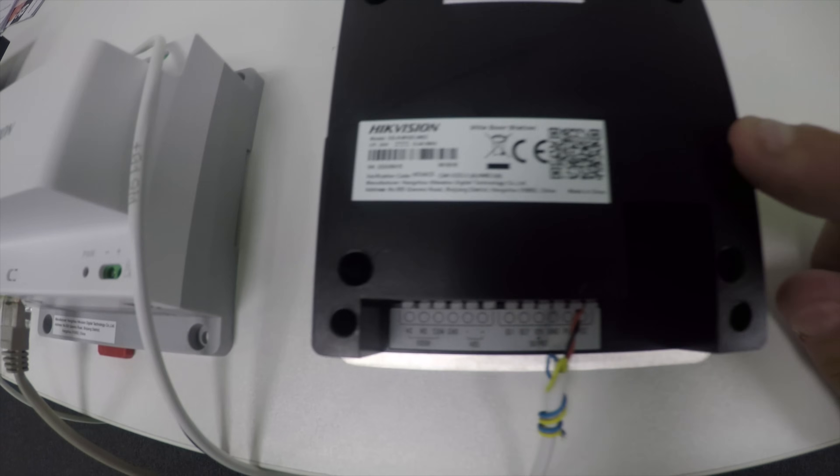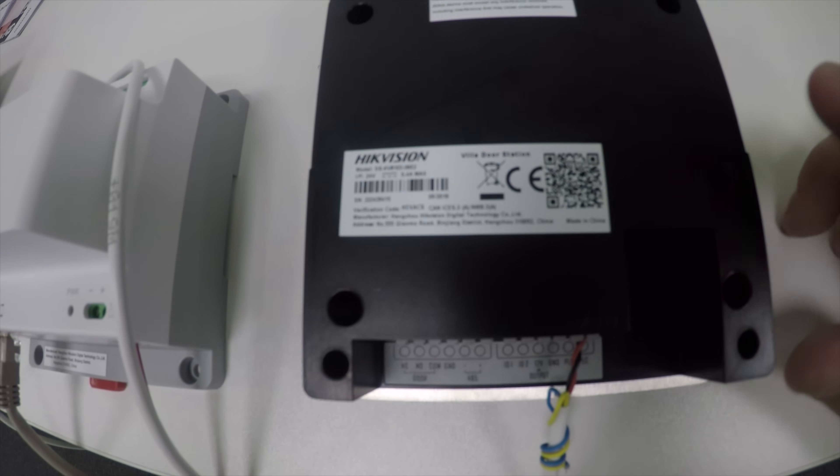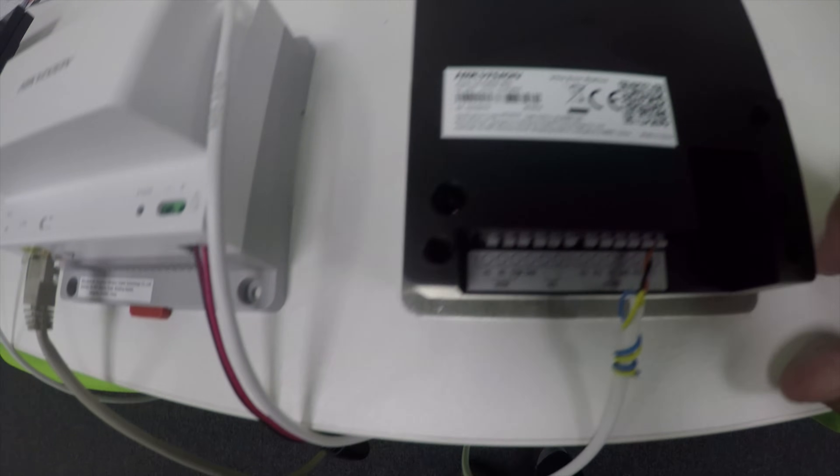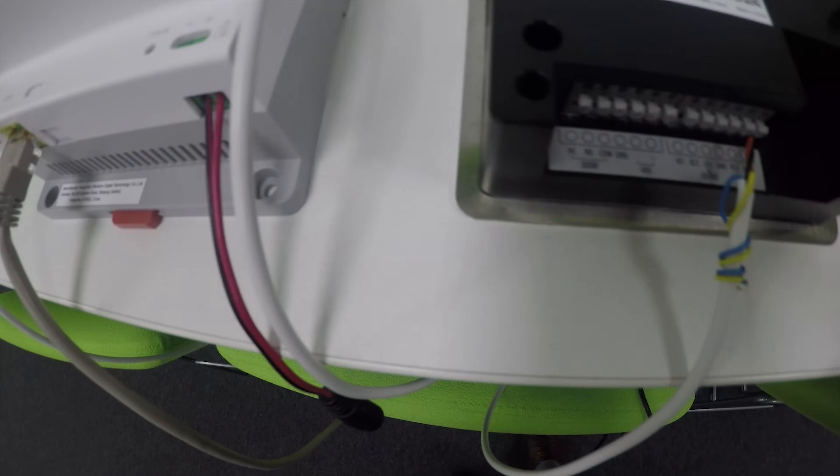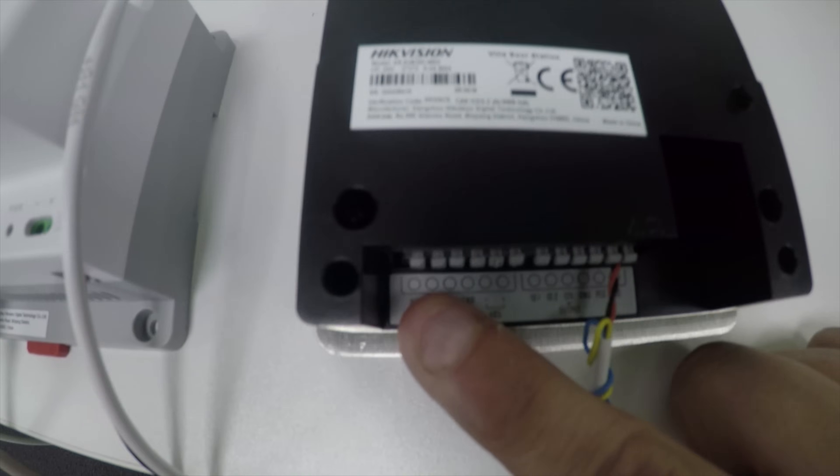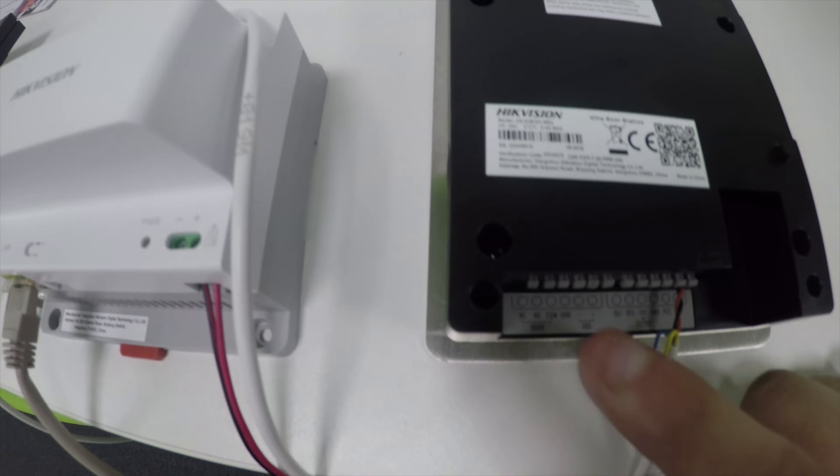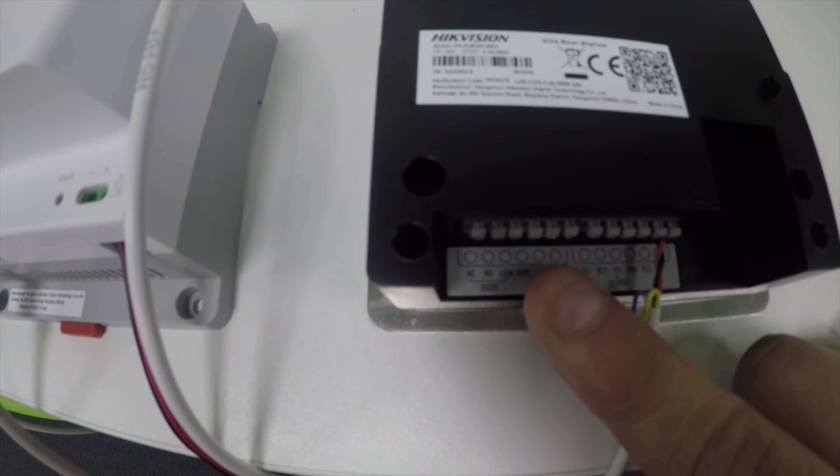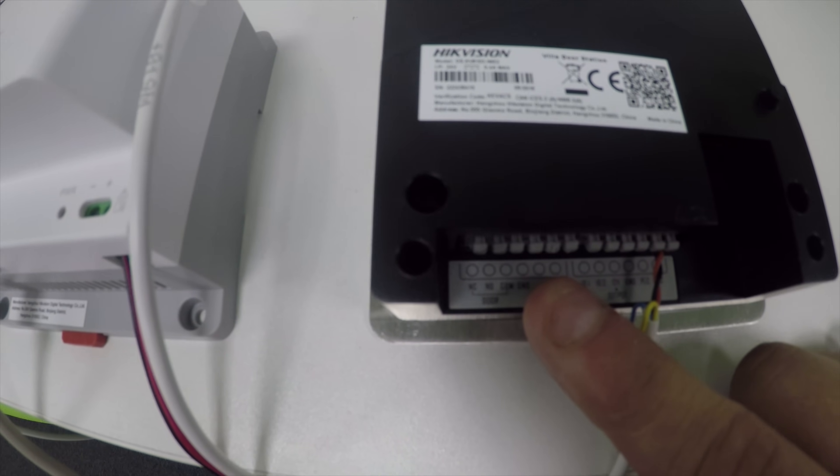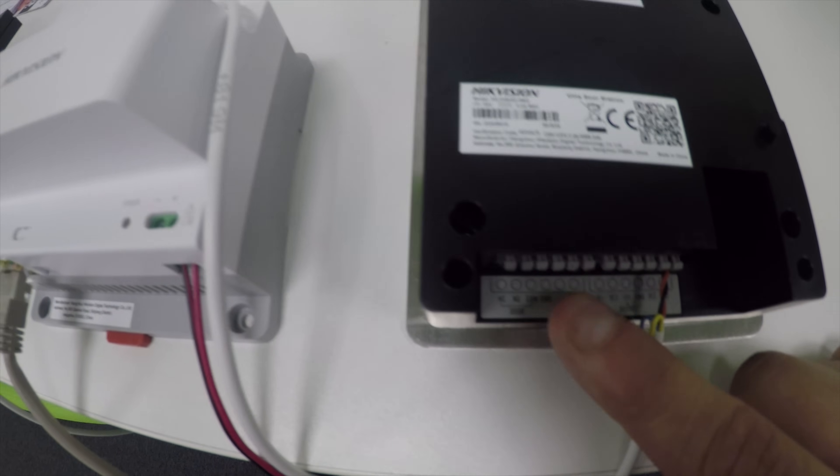You've got your outdoor station with a tamper switch that the case would hold in. It's got connections along the bottom: your lock relay, ground, RS-485 for the secure door module, and inputs for door contact and request to exit.